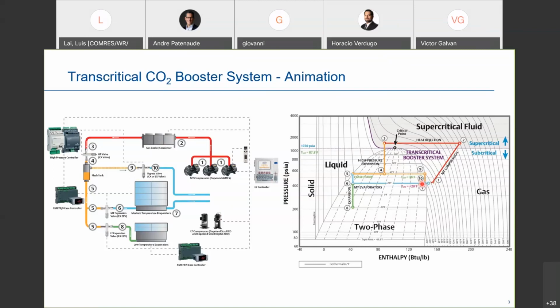Actually, there is a saturation there because it falls right inside the dome. So there's still a little bit of liquid left in that vapor, which is used for de-superheating a little bit. So that's an advantage. Down here, as the pressure goes through the low temp evaporator at maybe 200 pounds or minus 20, you go to the right chart from 8, it goes through the evaporator, it picks up heat until it gets to the saturated vapor line.